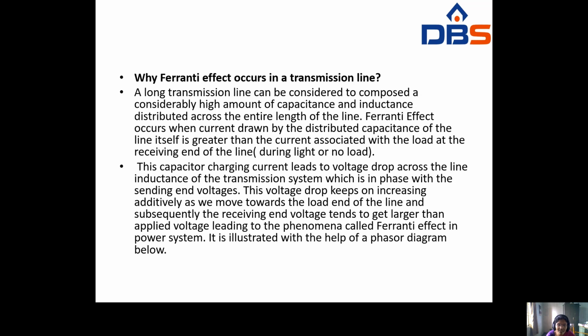The Ferranti effect occurs when the current drawn by the distributed capacitance of the line itself is greater than the current associated with the load at the receiving end of the line. That means whenever the transmission line has a light load or no load, the current drawn by the capacitance of the line itself is greater than the current at the load point. That effect is called the Ferranti effect.